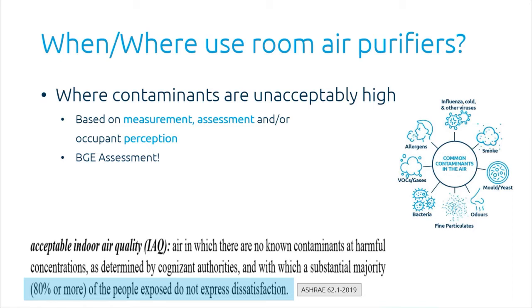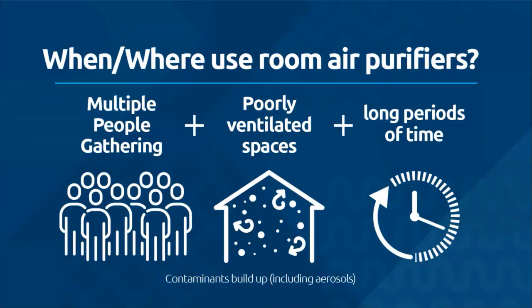ASHRAE, as part of their guidelines, says that if 80% or more of exposed people do not express dissatisfaction, then you have good indoor air quality. But if 80% or more do express dissatisfaction, then you don't, and you should be doing something about it. So there's a subjective component to air quality as well as a measured component. When and where do we use these? Fundamentally, where multiple people are gathering in poorly or inadequately ventilated spaces for long periods of time. So again, you have 30 students in a classroom. That classroom has some ventilation, some air changes and air flowing through it. But is it enough?